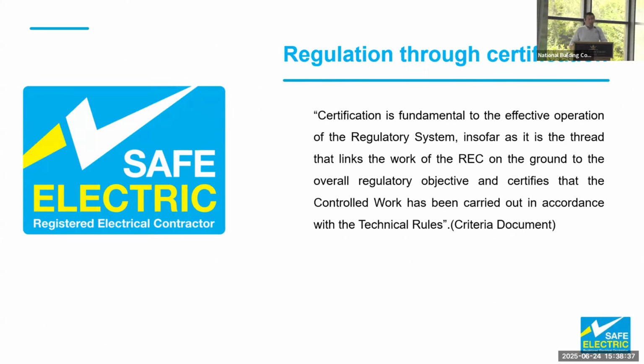So certification is probably one of the most important parts of our scheme. When you have a Safe Electric cert, it means your installation is compliant with the wiring rules and tests have been carried out in accordance with part 6 of those rules. There's a number of tests that have to be carried out to ensure the safety of the installation.